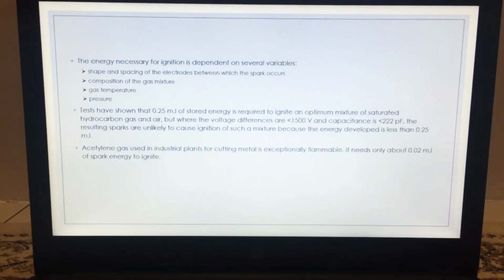The energy necessary for ignition is dependent on several variables. Firstly is the shape and spacing of the electrodes between which the spark occurs. Second is the composition of the gas mixture. The third is the gas temperature, and the fourth is pressure.